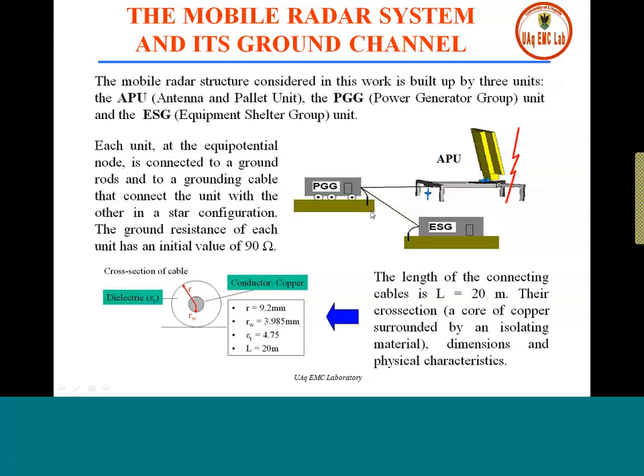Another important point is that the grounding impedance will depend on whether it rained the day before. This portable system will be placed on the ground, so depending on whether the soil is dry or humid, the grounding impedance will not be the same. It is not easy to design your radar system protection with a constant grounding impedance because it changes depending on the weather.